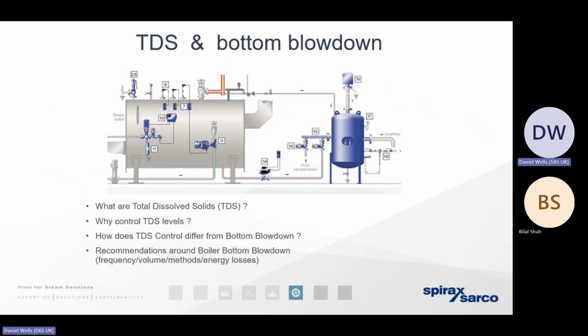In order to maintain the water chemistry, we perform what we call blowdown. So if you think of a steam boiler, think of it as a cup of tea. We put a spoon of sugar into the tea, we put a spoon of sand into the tea. And that represents the different cocktails of chemicals and minerals that are going to be present within the water locally. Some of the chemicals will dissolve, like the sugar, and some will just form as a particulate at the bottom of the boiler, like the sand. So we need to address both.